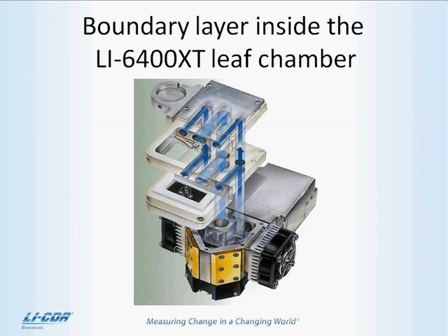The leaf chamber mixing fan of the LI-6400 vigorously circulates air over both sides of the leaf. Inside the LI-6400, the wind speed is much higher than typical field conditions. If you open the LI-6400 leaf chamber when it is running and listen, you will know what I mean. Under field conditions or in greenhouses, the stomates are not exposed to such high wind speeds.